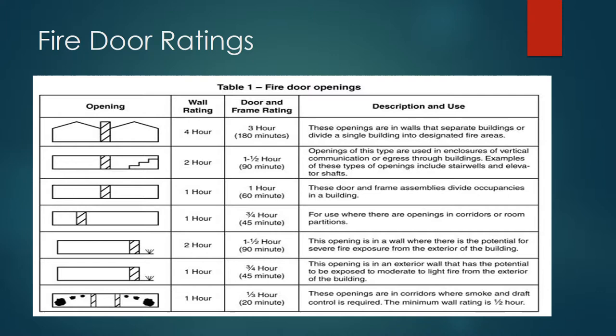Because that combustible load isn't present at the door, it won't add to the intensity of a fire there. On a wall, something burning against it focuses the fire and flames. That's why wall ratings are higher than door ratings. You're also not allowed to put combustible items on doors — no paper, boxes, wreaths — especially during seasonal times.